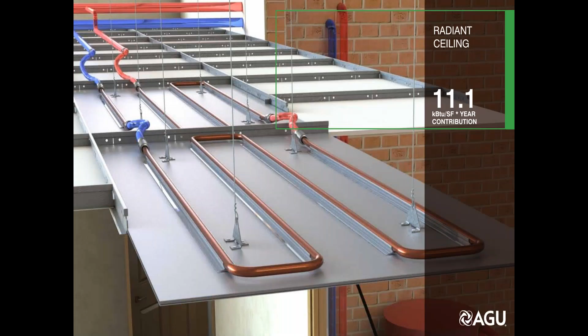It's a very simple system — essentially a metal ceiling grid with serpentine copper pipes on the back. Cooler water, not chilled water, is circulated in relatively small quantities through the piping, lowering the surface temperature of the ceiling. There's then a radiation exchange between the humans in the building and the ceiling. It's much different from air-based systems, where your body feels warm and cold air is blown onto your skin. This system is based on radiation — it would work even in a vacuum, with no air in the space, since it's a radiation exchange.